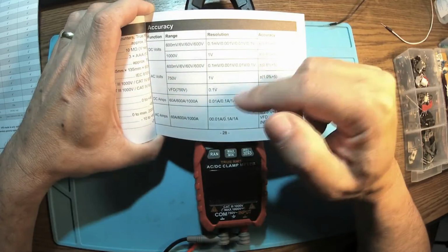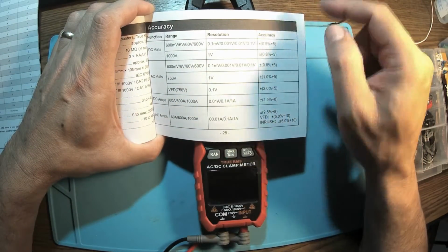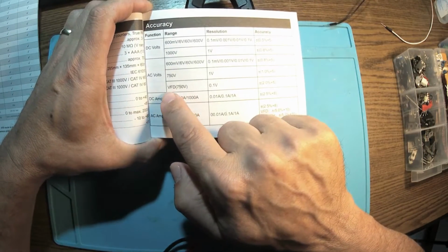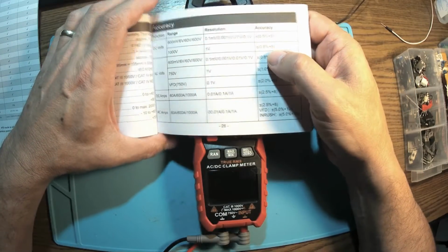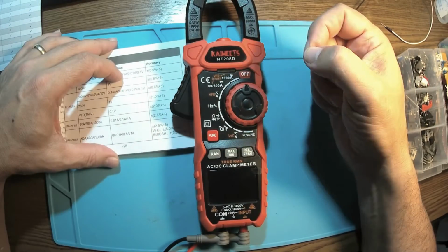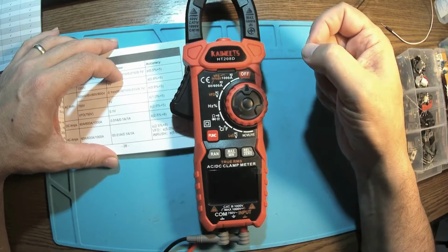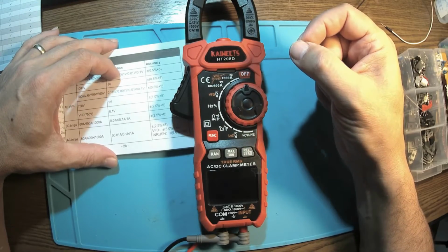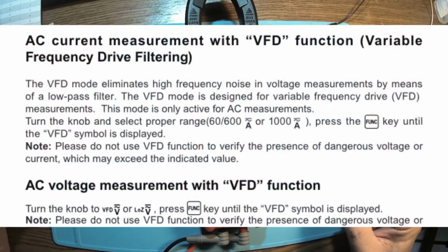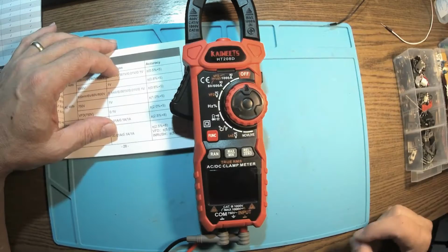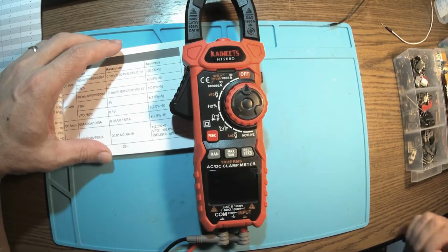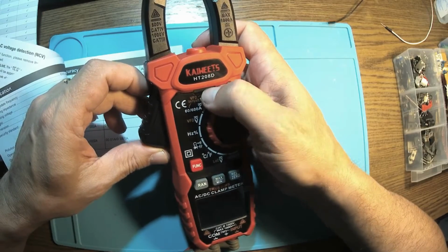AC, of course, from 0 to 750, and we also have this VFD function, which is very interesting. When we are measuring AC currents and voltages, there is a low pass filter, so it's cutting the interferences or the harmonics and other signals that mess with the measurements.